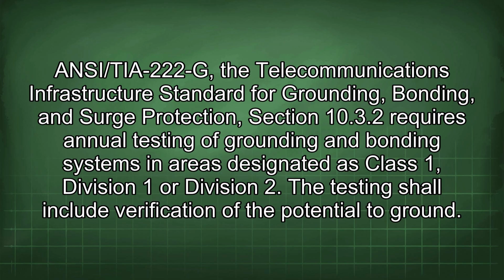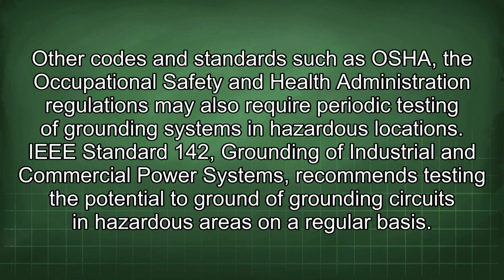ANSI/TIA 222G, the Telecommunications Infrastructure Standard for Grounding, Bonding, and Surge Protection, Section 10.3.2 requires annual testing of grounding and bonding systems in areas designated as Class 1, Division 1 or Division 2. The testing shall include verification of the potential to ground. Other codes and standards, such as OSHA, the Occupational Safety and Health Administration regulations, may also require periodic testing of grounding systems in hazardous locations.